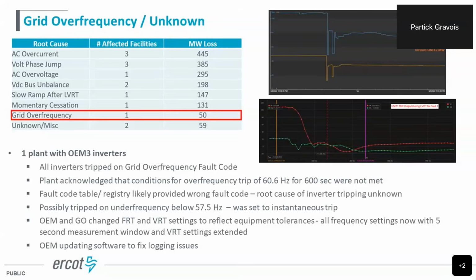They did go through with the GO and the OEM to really work on the FRT and VRT settings to reflect the actual equipment tolerances instead of just having them loosely based on the PRC 24 or nodal operating guide requirements. So they have extended these out pretty significantly. There's actually 2 of these plants that have done this work. They've set all of their frequency settings to now have a 5-second measurement window, because there really is no technical reason for inverter protection that these things need to be tripping off for a frequency, especially anywhere near what our requirements are for conventional generation. So they've extended those out. They've also extended out their voltage ride-through settings as well. And they have fixed the logging issues.